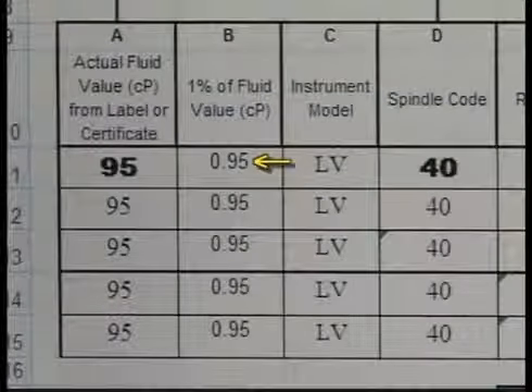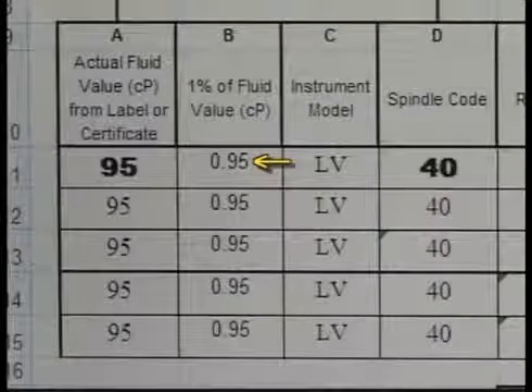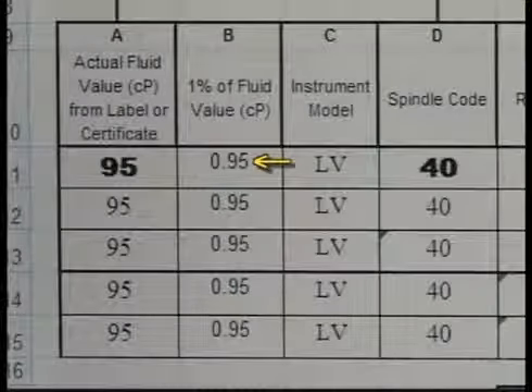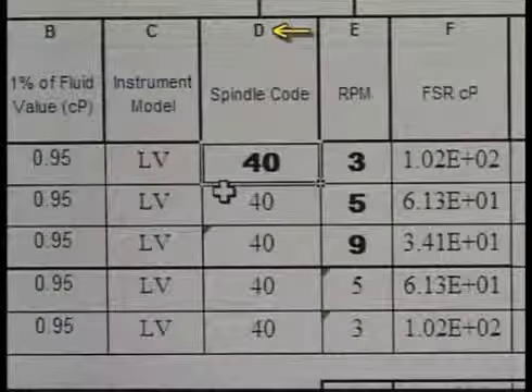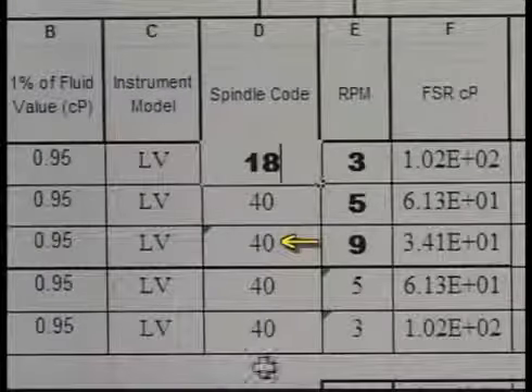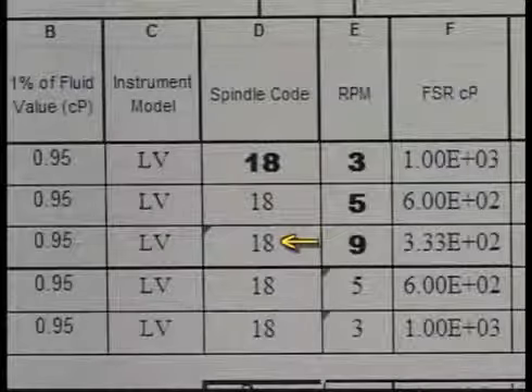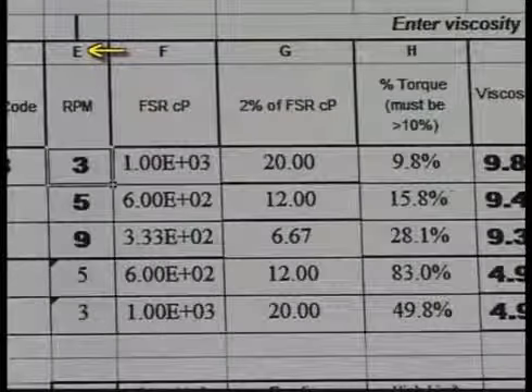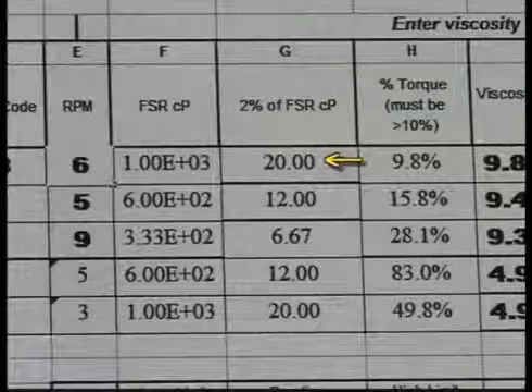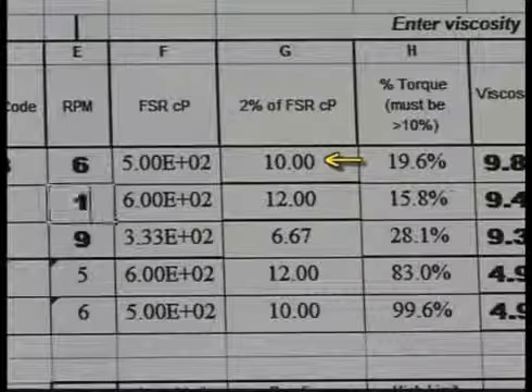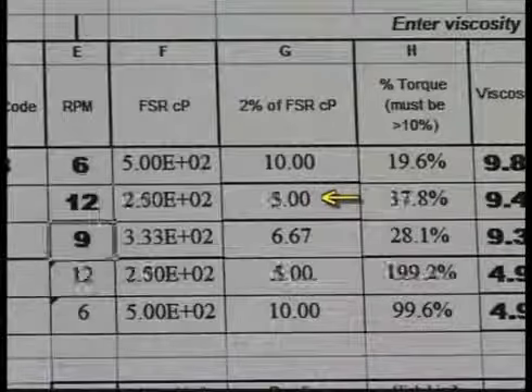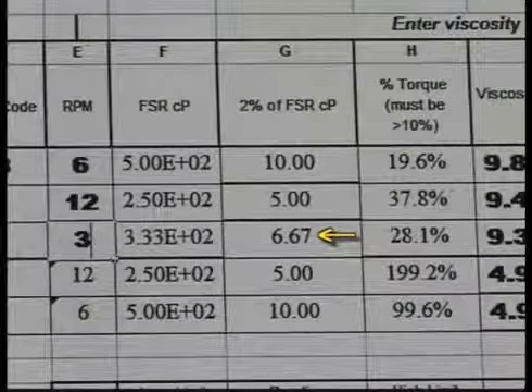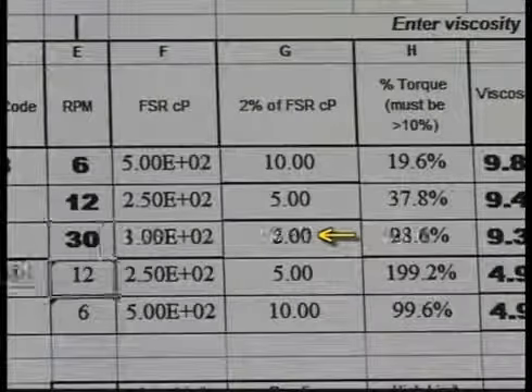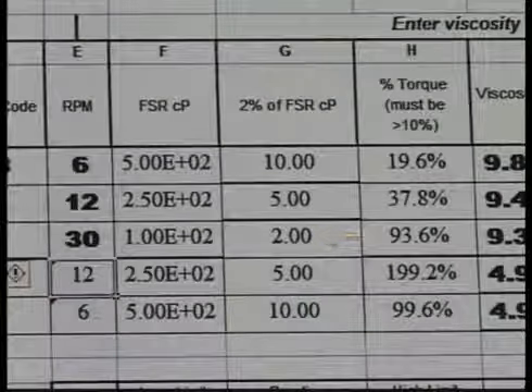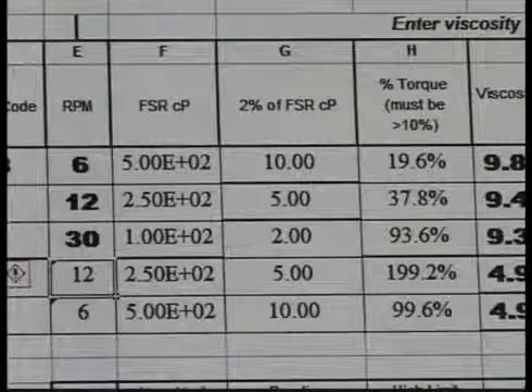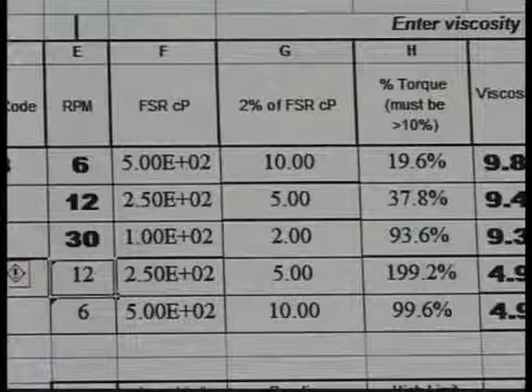You can see the 1% fluid value column will update based on this entry. This is the accuracy of the fluid. Enter the spindle code in column D. Again, the fields in this column will automatically update. Enter the 3 speeds you will be running in column E and observe that the 2% tolerance of full-scale range, based on plus or minus 1% instrument accuracy and plus or minus 1% accessory accuracy, in column G is updated. This is the accuracy of the viscometer and small sample adapter at this range.